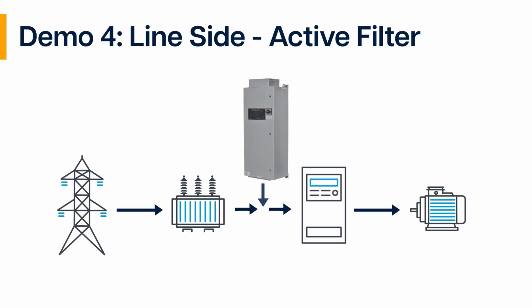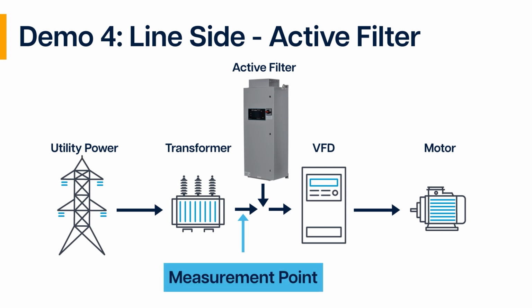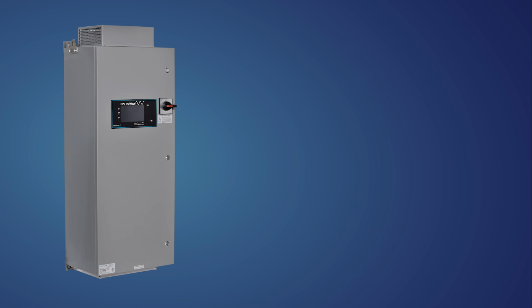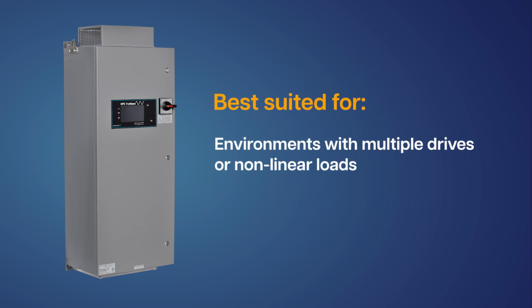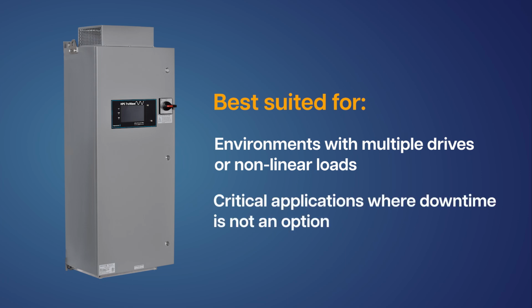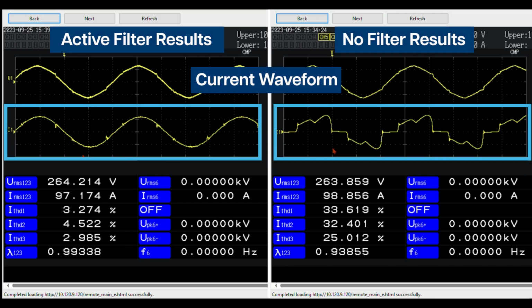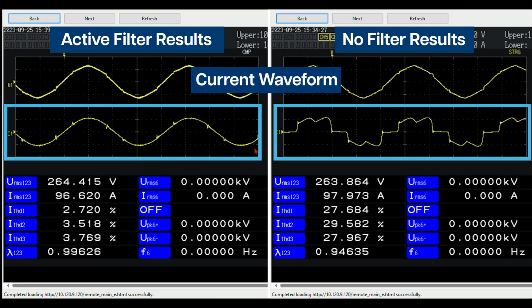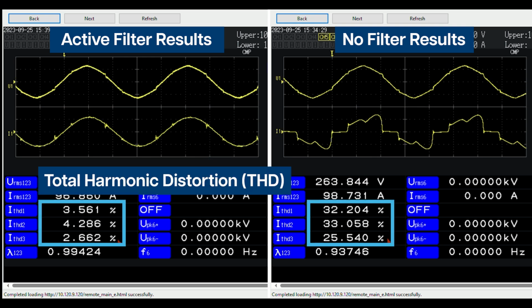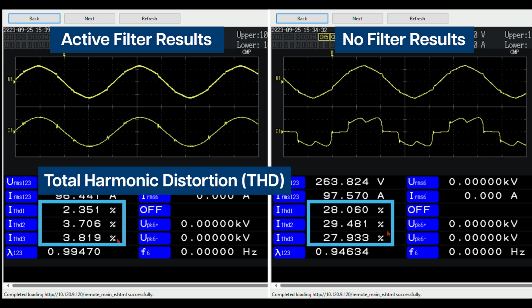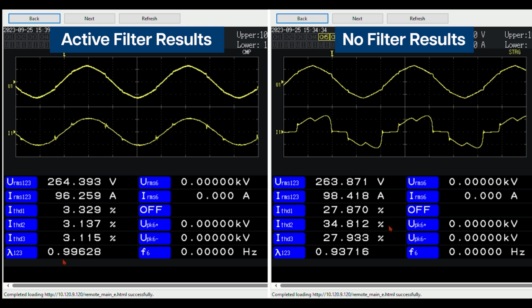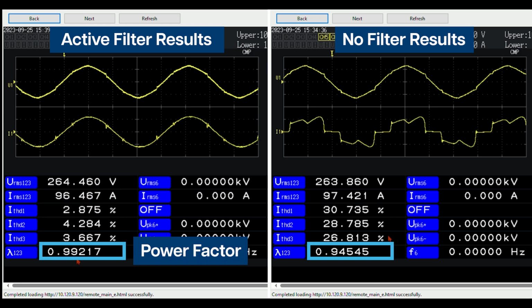For Demo 4, we introduce the most sophisticated solution, the active harmonic filter. Active harmonic filters are best suited for environments with multiple drives or nonlinear loads, and critical applications where downtime is not an option. This parallel-installed device employs a current sensor to identify and neutralize harmful harmonics, ensuring operational continuity even if the filter is offline.